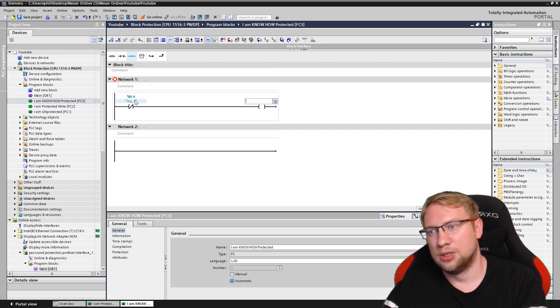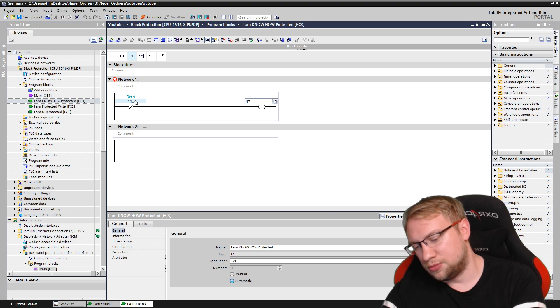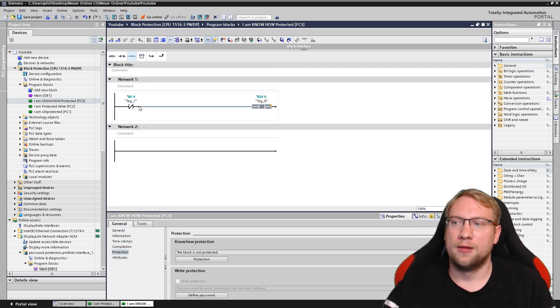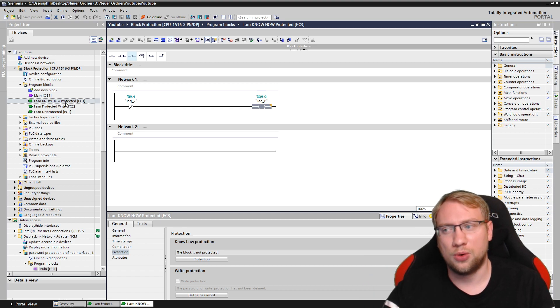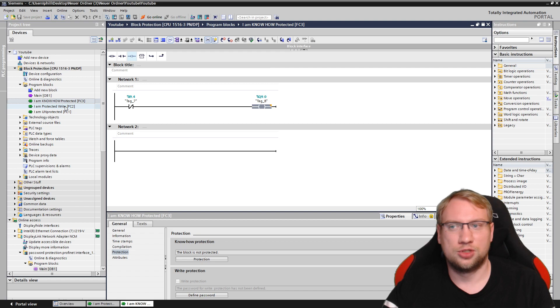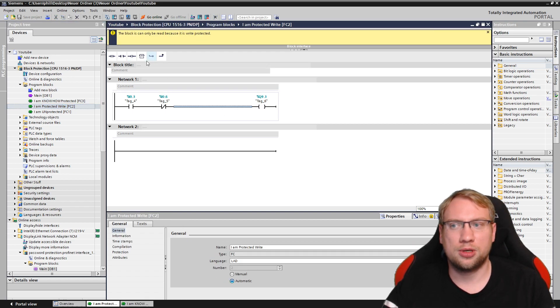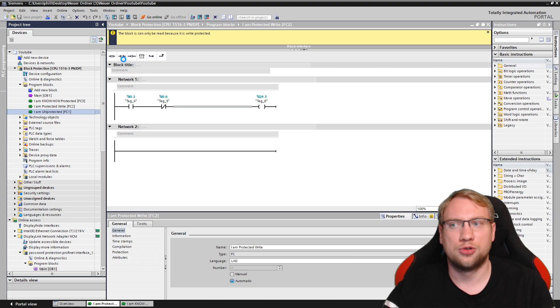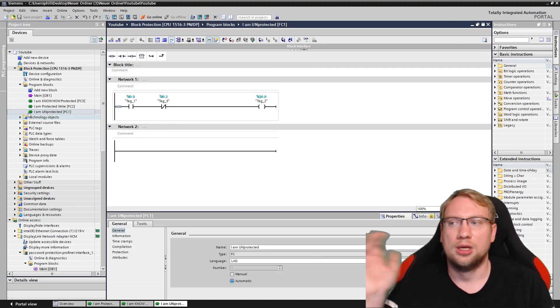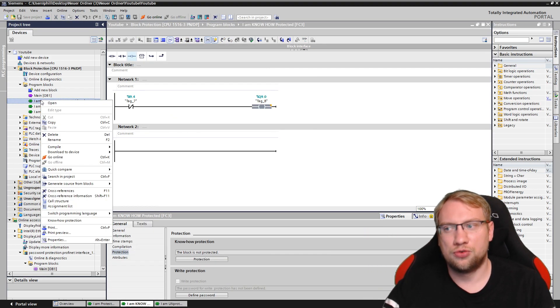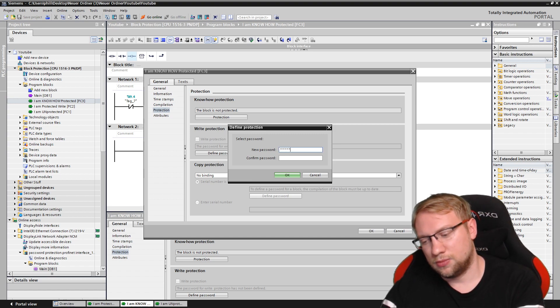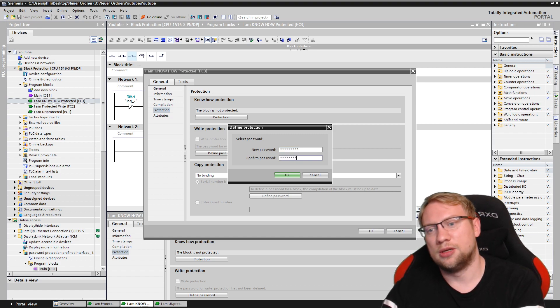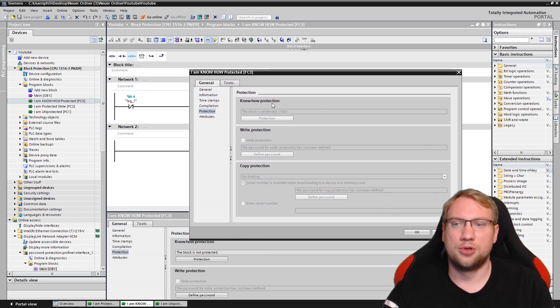I'll just make some program here. This is my 'I am protected' block — the one that should have know-how protection. Right now I can still change it. For know-how protection, right-click, Properties, Protection, and we have know-how protection. If I turn the protection on, I have to set a password. And now it is know-how protected, and also the block is protected.